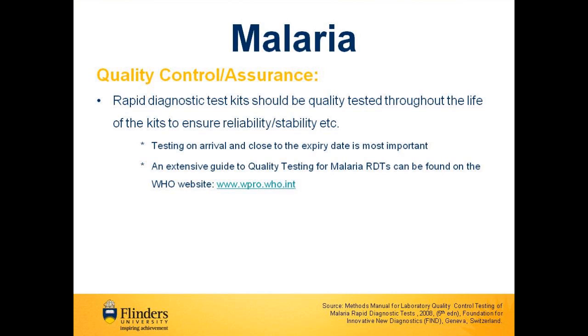It is important that RDTs are quality tested throughout the life of the kits to ensure their reliability and stability. At least one quality control test should be performed upon arrival of every new lot number of RDT and also when RDTs are getting close to their expiry date. An extensive guide on quality testing for malaria RDTs can be found at the World Health Organisation website.